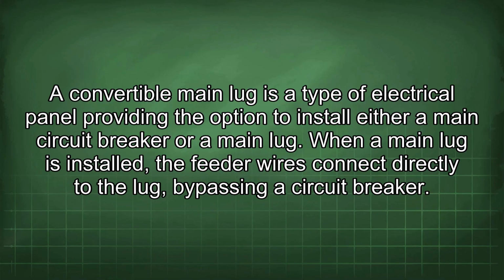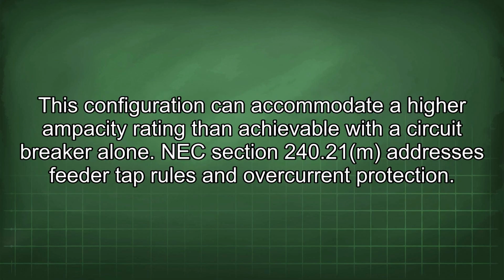A convertible main lug is a type of electrical panel providing the option to install either a main circuit breaker or a main lug. When a main lug is installed, the feeder wires connect directly to the lug, bypassing a circuit breaker. This configuration can accommodate a higher ampacity rating than achievable with a circuit breaker alone. NEC Section 240.21 addresses feeder tap rules and overcurrent protection.